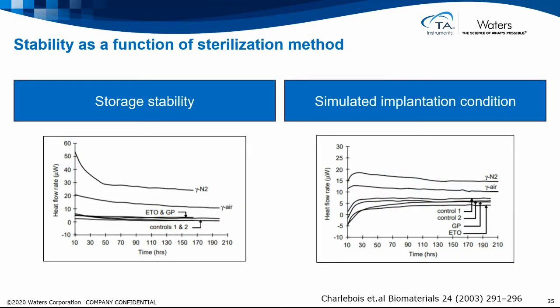We see here stability testing as a function of storage stability. In the first one, we have different sterilization methods. The control that's unsterilized and ethylene oxide or gas plasma sterilization yield almost no reaction at all, but samples that have been gamma irradiated, both in nitrogen and air, show a much higher reaction rate in the microcalorimetry. Now you can see that this is measured for a very long time. Typically you do not need to measure for this long period of time, but to learn about the material, sometimes they are measured for long periods of time.